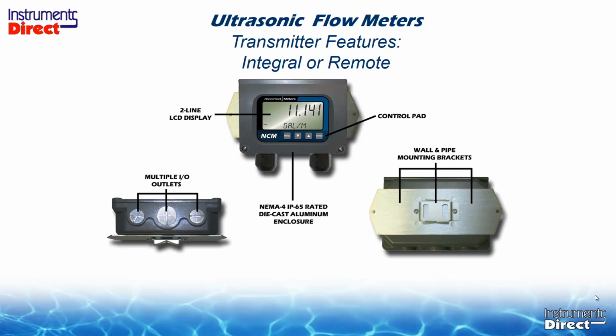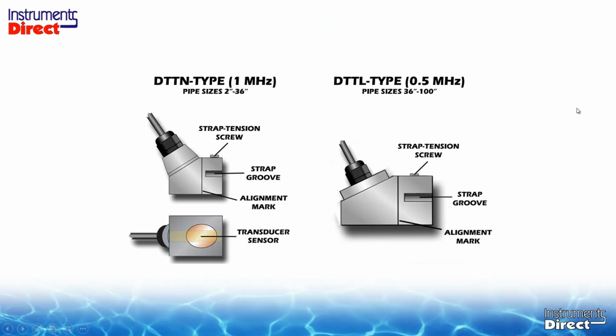Now, let's check out the features. The NCM series comes in a small die-cast aluminum enclosure that has an LCD display of rate and total. It's a wall-mounted enclosure, and you also need a set of strap-on transducers. The transducers for 2-inch and larger are adjustable for different pipe sizes. The DTTN is a 1 megahertz transducer used on pipe sizes 2 inches up to 36 inches, sometimes larger depending on pipe conditions.